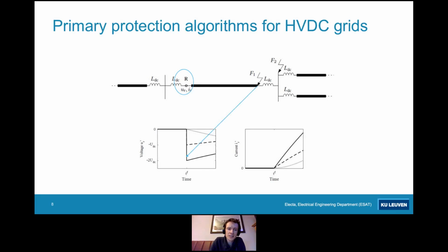You can see this clearly in the voltage, because for an internal fault on the line, we have a high dv/dt, while for a fault external to the line, so a fault beyond this inductor, this slope of the voltage is very much lower. And we can use that in an algorithm to discriminate between those faults. What we found was that the voltage signal was more robust to develop our algorithms on than the current, but we still use the current to determine the direction of the fault relative to the relay.